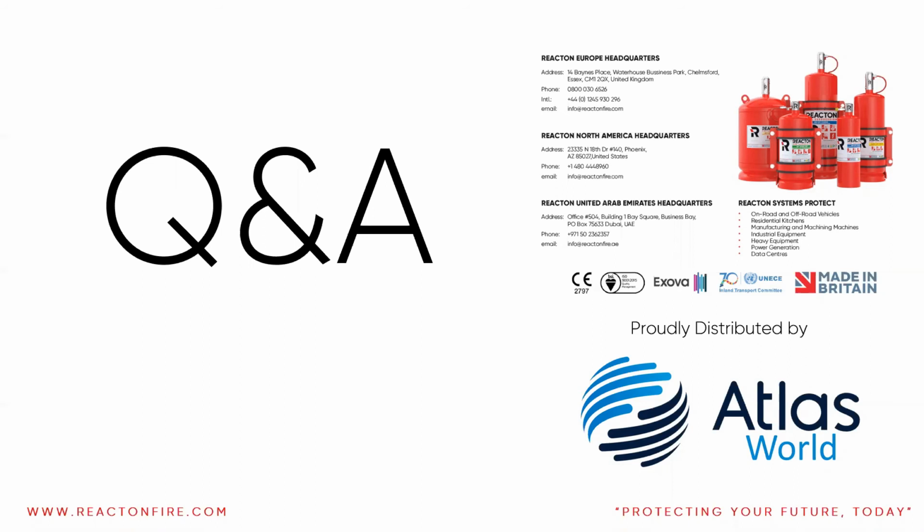Again, the 6-month check is typically something that can be done visually. It doesn't require too many parts, and anything that may have happened over that time from an external factor, it gives you the chance to replace and just make sure the system's in tip-top condition, really. As I say, mainly visual inspections, as it is a pressurized vessel. We can visually check and run through all of the detection tube to make sure nothing's rubbing on any components on the machine, or if the machine's been adapted in any way, shape or form.